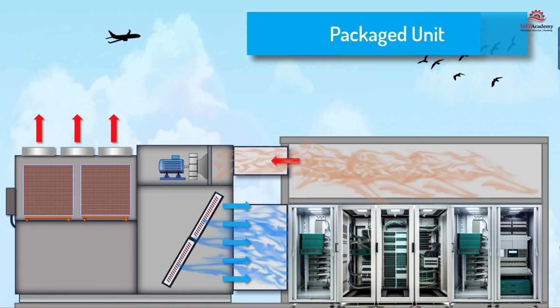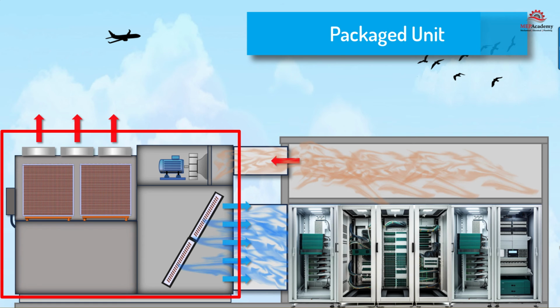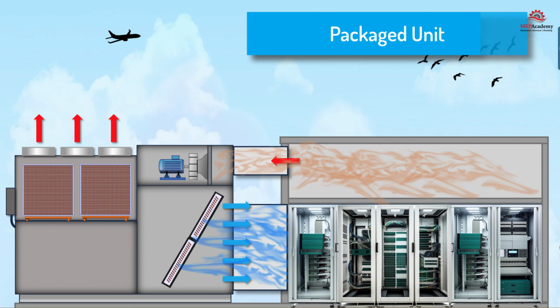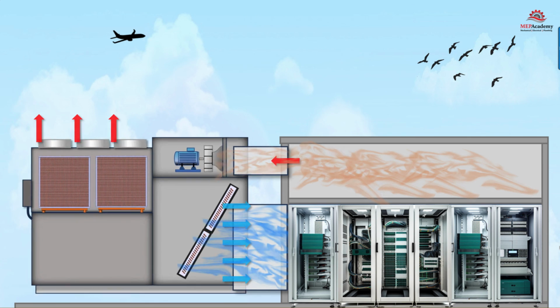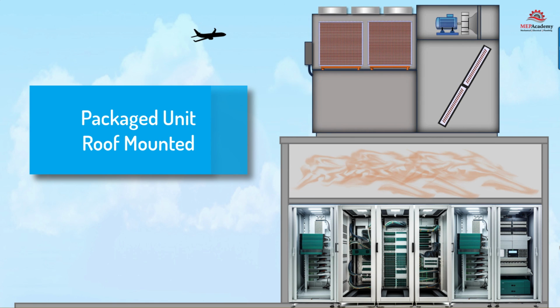Packaged units. Another configuration is the packaged unit, where the condenser, compressor, evaporator, and refrigerant pump are all housed in one larger unit. The unit can be installed on the side of a building, and the supply and return air ducted into the data center. Some form of isolation between the supply and return is required to avoid short-circuiting of the air. There is also a package unit version that can sit on the roof of the building and be ducted to the data center space. The same consideration needs to be made to ensure that the supply and return air pathways don't short-circuit before entering the IT equipment.